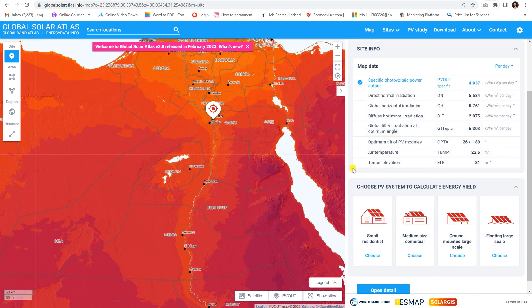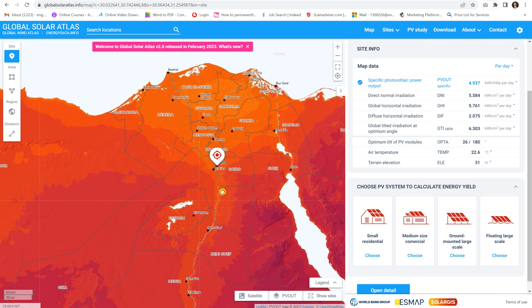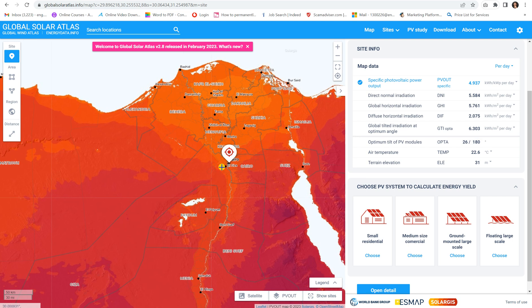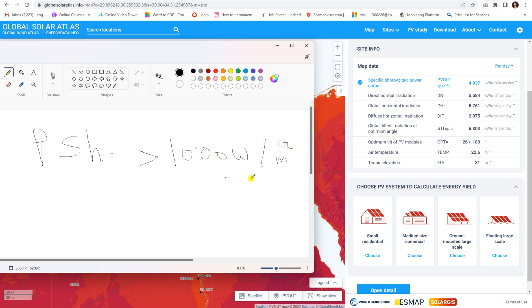The Global Tilted Irradiation at optimum angle represents kilowatt-hour per meter squared. The GHI and GTI are used to get the peak sun hours. Peak sun hours means the number of hours in a day during which we have irradiation of 1000 watts per meter squared or higher. This 1000 W/m² corresponds to the STC condition of irradiation.